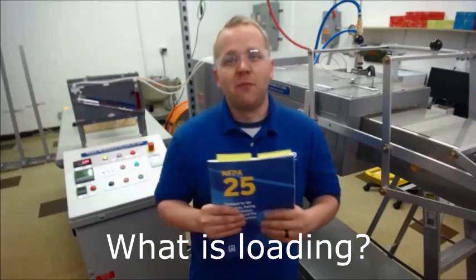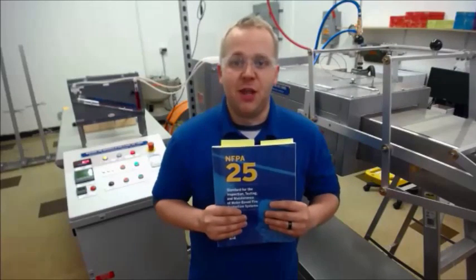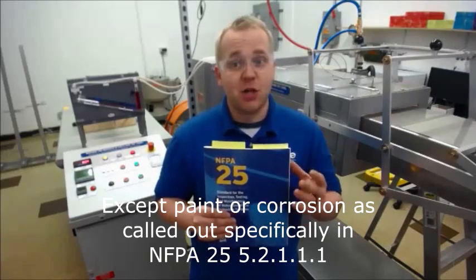So what's loading? If you're using NFPA 25, you probably already flipped to Chapter 3 definitions to look for loading, but there isn't a definition there. Dyne defines loading as debris on the head — any foreign material that wasn't there when it was made, except paint or corrosion.